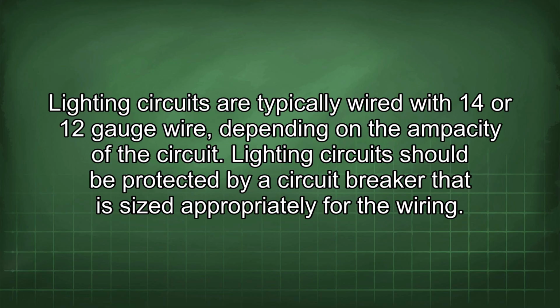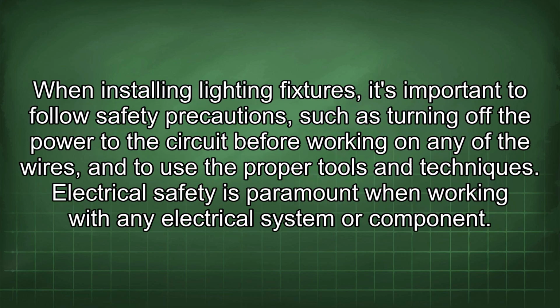Lighting circuits are typically wired with 14 or 12 gauge wire, depending on the ampacity of the circuit, and should be protected by a circuit breaker sized appropriately for the wiring. When installing lighting fixtures, follow safety precautions such as turning off the power to the circuit before working on any wires, and use the proper tools and techniques.